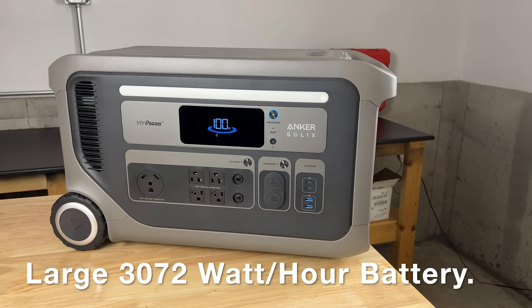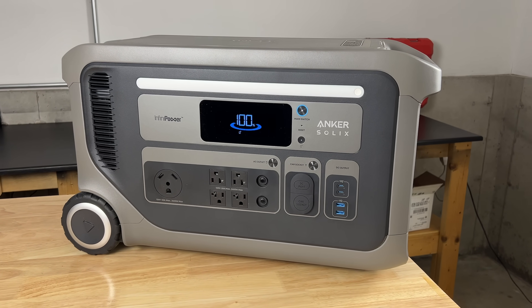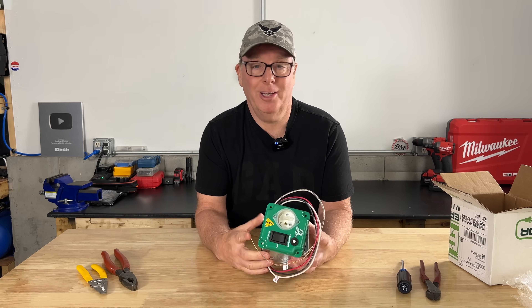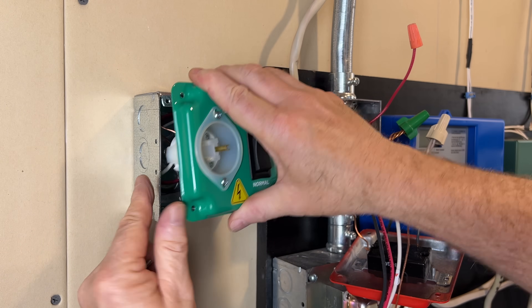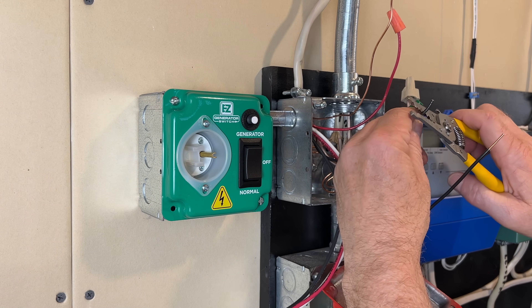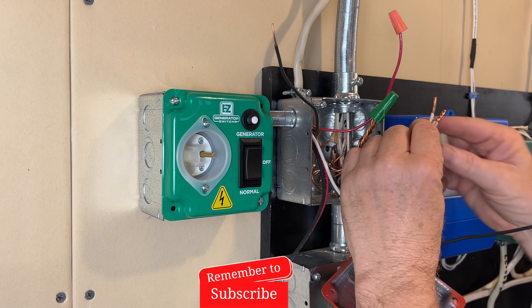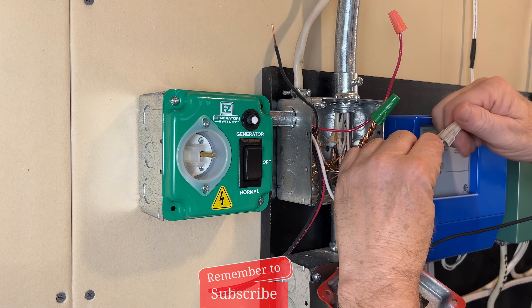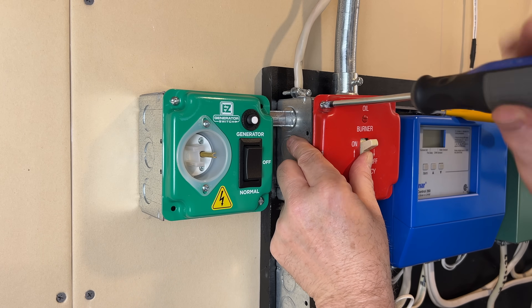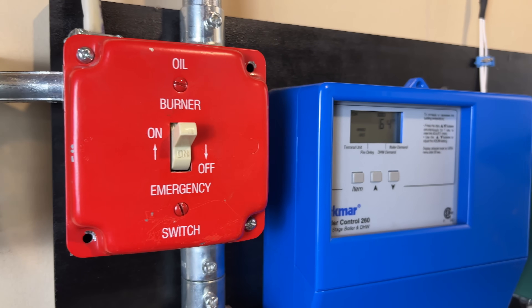With its 3072 watt-hour battery, the F3000 should keep the boiler running for a long time. We'll find out just how long it keeps it running in a few minutes. I've made a complete wiring and installation video for the EZ Generator Switch to help you install a similar setup at your home — I should have that video up soon so stay tuned. I installed the EZ Generator Switch just ahead of the safety switch, because all the safeties and boiler controls will still need to work while on backup power.